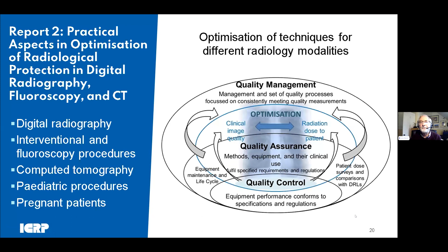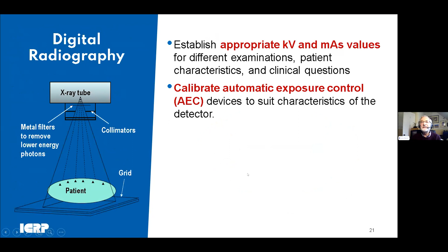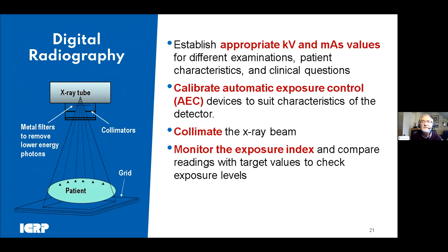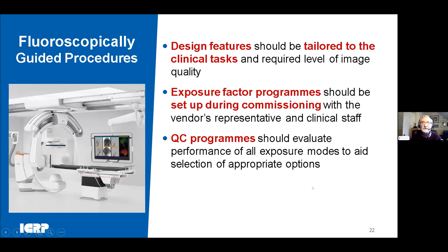So looking briefly, for digital radiography, we're establishing the appropriate kV and mAs values, calibrating the automatic exposure control devices, collimating the X-ray beam, monitoring the exposure index, and checking them against target values. For fluoroscopy, we'll be looking at the design features. Are they tailored to the clinical tasks? Exposure factor programs should be set up during commissioning with the application specialist. And then the QC program should evaluate performance of all the exposure modes and the selection of appropriate options.